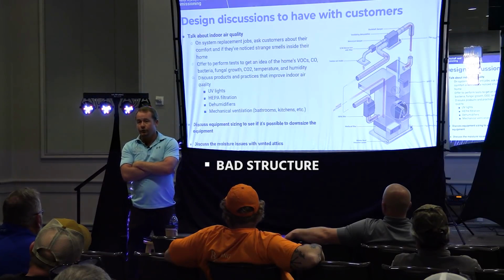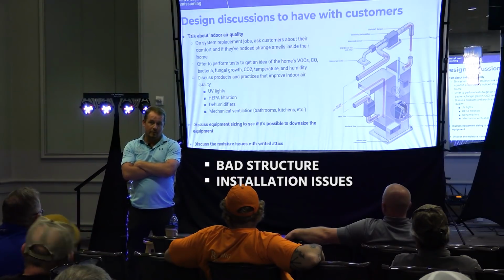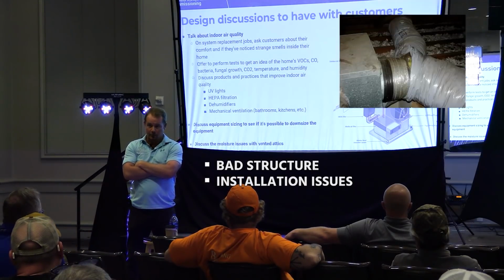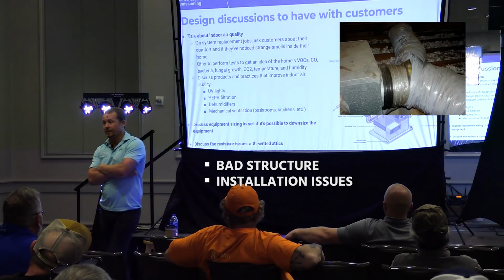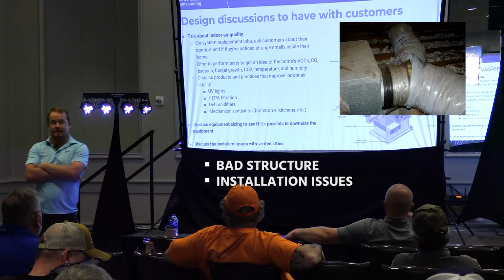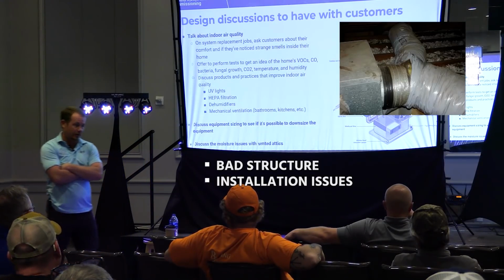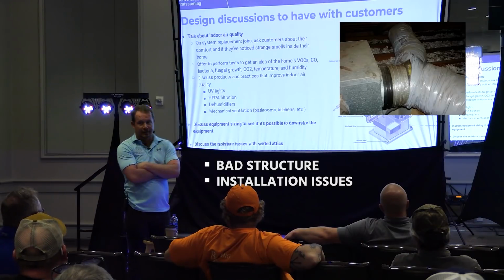So that's one. Two would be installation issues with the equipment - that includes things like leaky ductwork, the equipment not set up properly, the system not charged properly. Anything that makes the equipment not work right is definitely on the list for dehumidification issues.